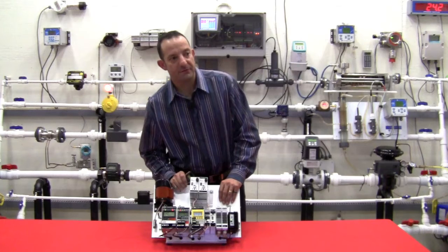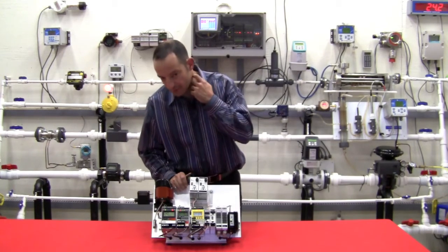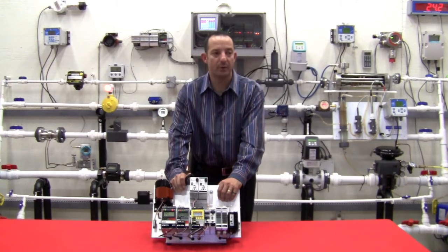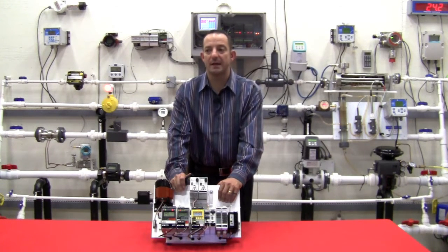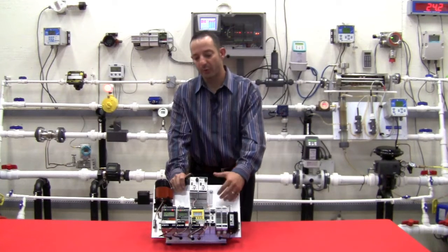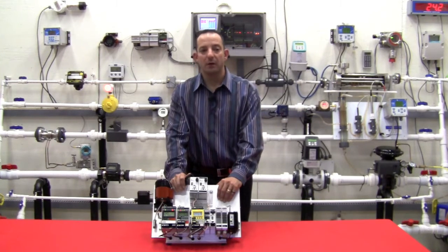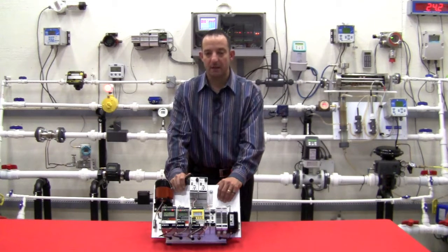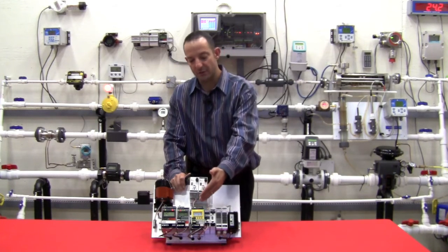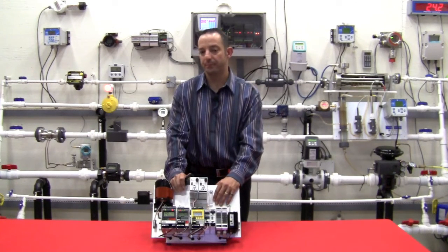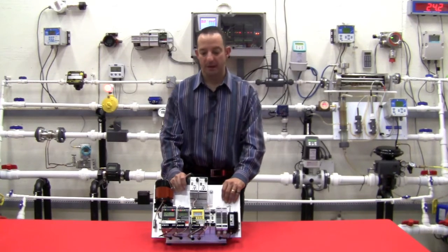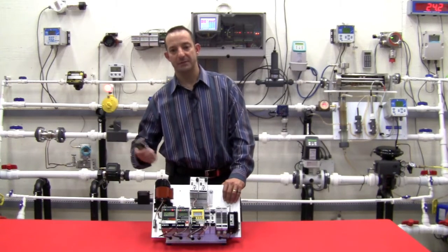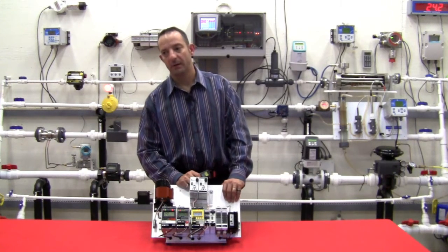Another feature to emphasize is that on the microprocessor-based units, we have linearization available for nonlinear signal inputs. So if your customer has a spherical tank and they want to bring in a level signal, but alarm on volume in that tank, you can linearize the input and then set your trip points based on volume. Going back to the analog output, now you could reproduce that analog output signal to the control system as volume and not raw level. And that's a big help too.